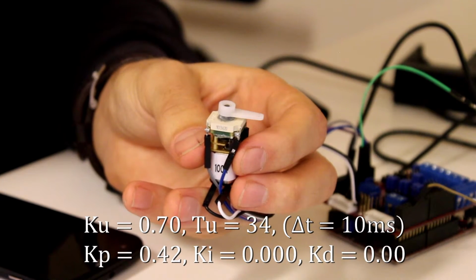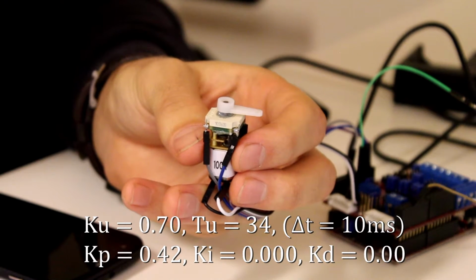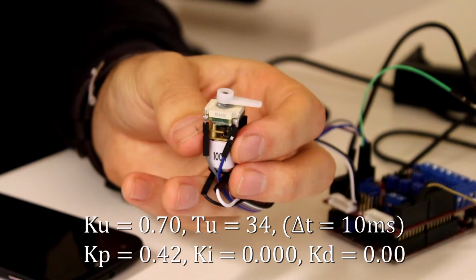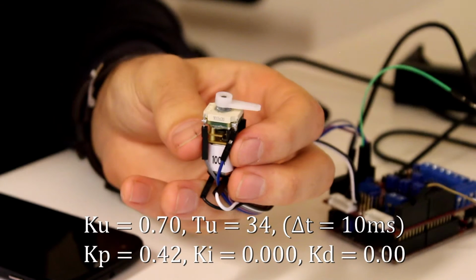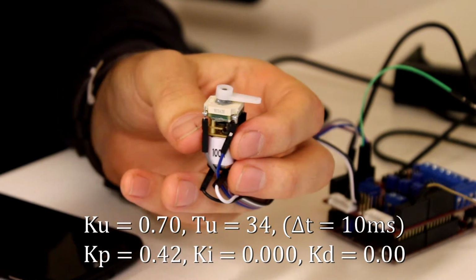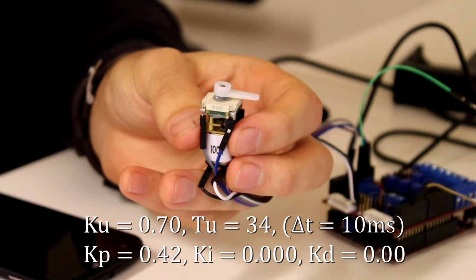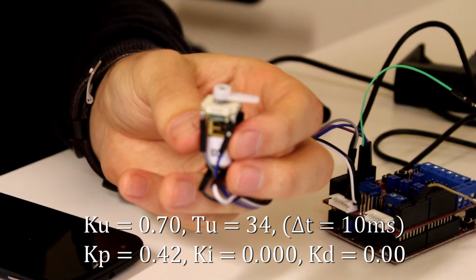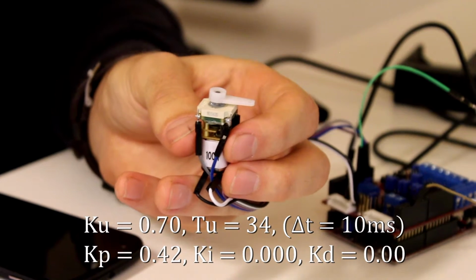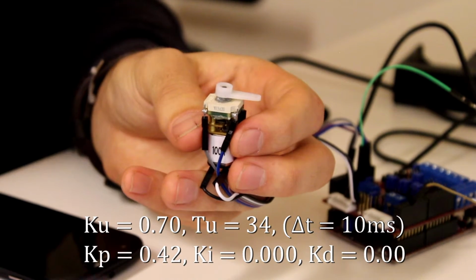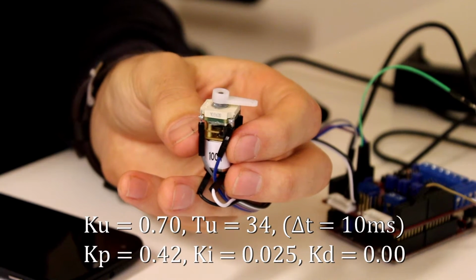This is what we end up with. Error of minus 24, not very good. For I, we use 1.2 times Ku divided by Tu, Tu being the period of 34. That is 1.2 times 0.7 divided by 34, which is 0.025, which is also not very good.